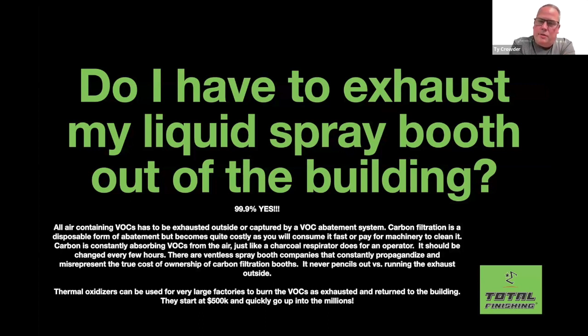The other kind of abatement out there for VOCs is what Sal had just said, thermal oxidizers. Okay. So a thermal oxidizer is a very large system. It essentially is an afterburner. So the exhaust stack goes through this afterburner. It goes across a big flame. It actually has big carbon ceramic balls inside of it that collect the gas. It goes over to a section that rotates to a hot flame, incinerates the VOC, goes over, cools, and comes back as kind of the big rotating thing.